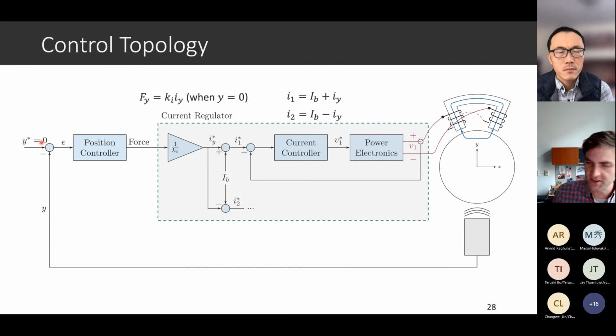I've got a reference position, and in a magnetic bearing your reference position is always zero—you always want the shaft in the center of the air gap. I compare the reference to the measurement and get an error in the shaft position, which I feed into a position controller or regulator. Out comes a force command, and I convert that force into a current that I want to flow in my bearing. This whole box here is really just a current regulator.